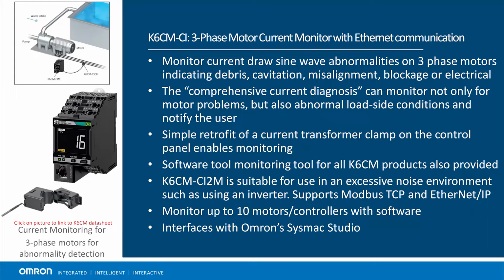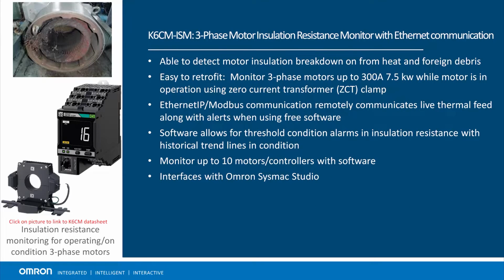The K6CM CIM uses a clamp type current transformer to read the motor's current waveform. Changes in the waveform can indicate load irregularities, cavitation, or misalignment. The K6CM ISM uses a clamp type zero-phase current transformer to monitor leakage current at the secondary side of an inverter. Fluctuating leakage current is an indication of motor insulation deterioration.